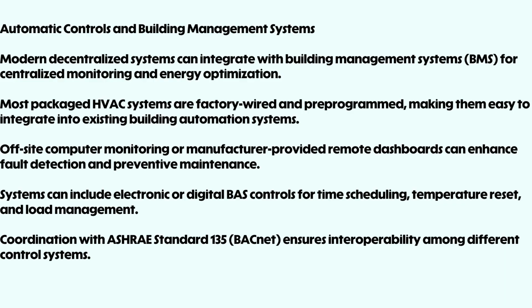Modern decentralized systems can integrate with building management systems, BMS, for centralized monitoring and energy optimization. Most packaged HVAC systems are factory-wired and pre-programmed, making them easy to integrate into existing building automation systems. Off-site computer monitoring or manufacturer-provided remote dashboards can enhance fault detection and preventive maintenance. Systems can include electronic or digital BAS controls for time scheduling, temperature reset, and load management. Coordination with ASHRAE Standard 135, BACnet, ensures interoperability among different control systems.